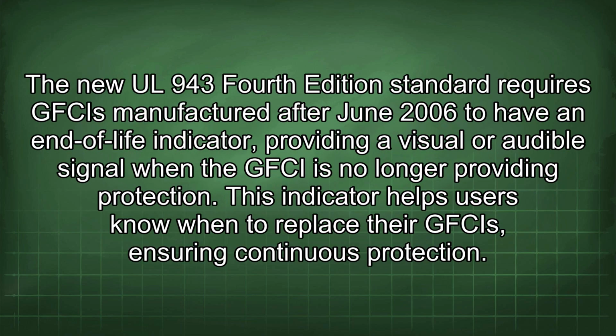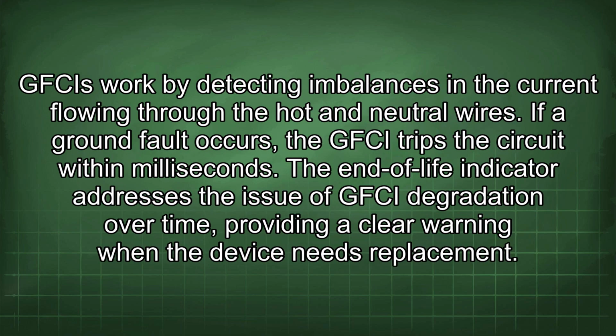The new UL 943 4th edition standard requires GFCIs manufactured after June 2006 to have an end-of-life indicator, providing a visual or audible signal when the GFCI is no longer providing protection. This indicator helps users know when to replace their GFCIs, ensuring continuous protection. GFCIs work by detecting imbalances in the current flowing through the hot and neutral wires. If a ground fault occurs, the GFCI trips the circuit within milliseconds. The end-of-life indicator addresses the issue of GFCI degradation over time, providing a clear warning when the device needs replacement.